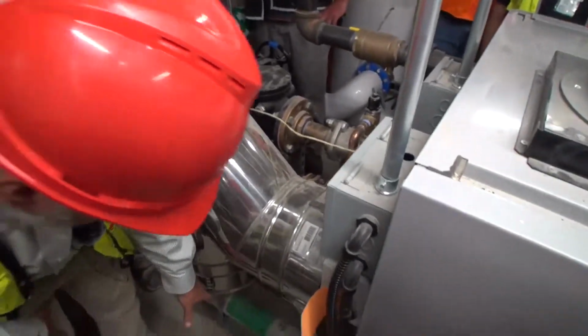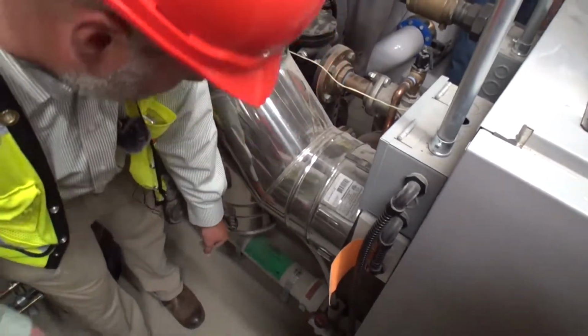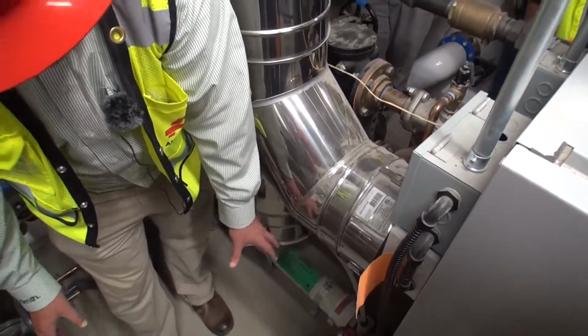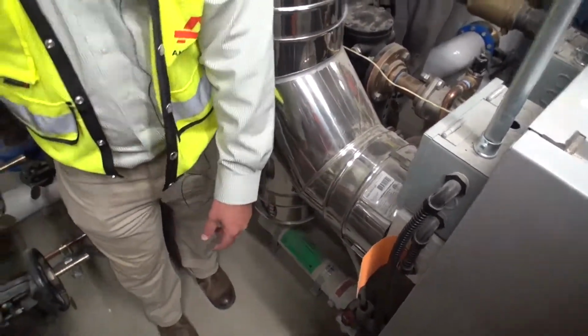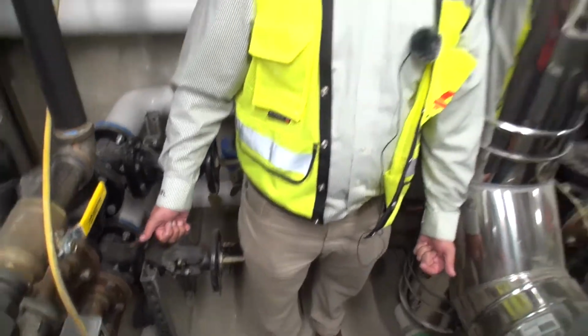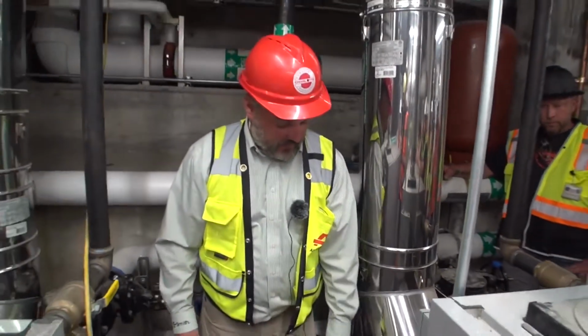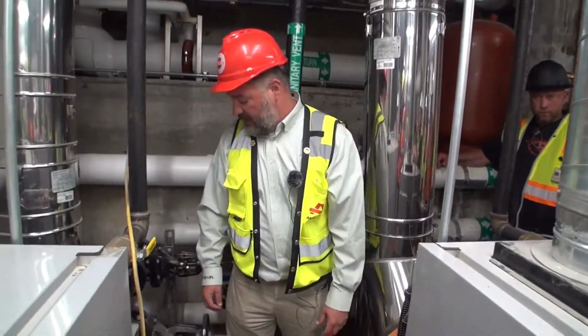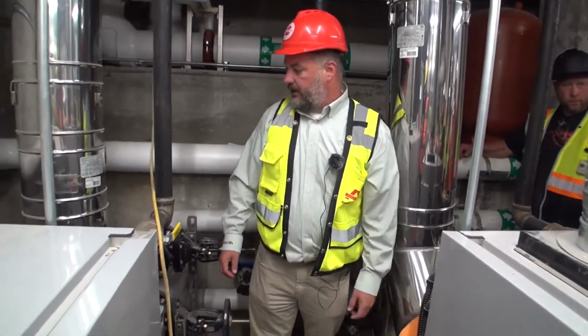Check with your manufacturer. I know with ours, those aren't going to be ours, but typically your neutralization should be looked at 1 to 2 years on the replacement side of it, so that we can make sure we're basically nullifying the condensation going through your drain line on here.